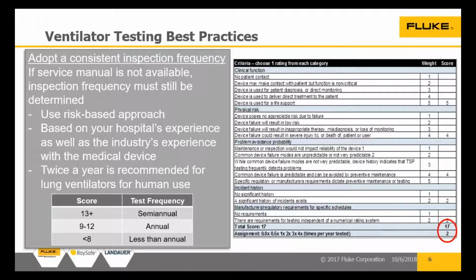This is a yes or no question: are there manufacturer or regulatory requirements for testing schedules? If there's an IEC standard, the answer has to be yes, because the manufacturer will be following that standard, especially for devices that need to pass muster with the US FDA before reaching us.